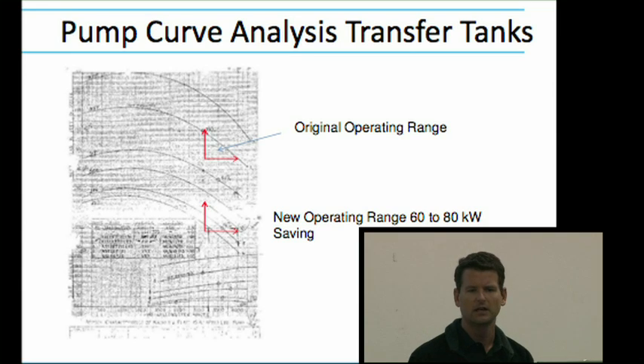On the transfer tank, I was talking about pumping to 2 different levels. In that situation, this is the original pumping operating range. All I did on 2 of the pumps is trim the impellers and move the operating range down to there, saving 60 to 80 kilowatts. Then I put 1 new pump in dedicated to the A reservoir, which is up on the hill.